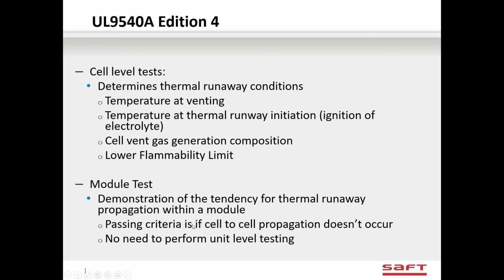It says if you pass, if there's no cell to cell propagation, it doesn't occur and there's no need to perform unit level testing. That's not true. You have to also meet one more criteria that says there is no thermal or no flammable gas emitted to be able to stop at the module test.